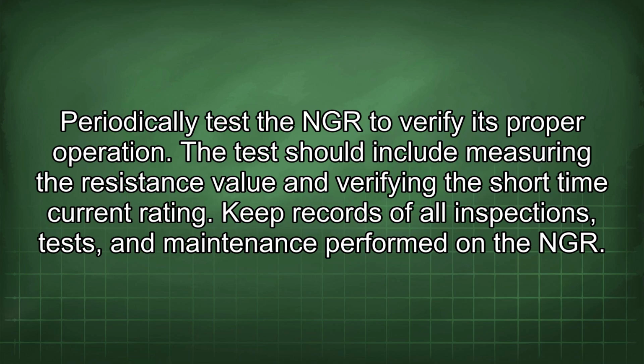Periodically test the NGR to verify its proper operation. The test should include measuring the resistance value and verifying the short-time current rating. Keep records of all inspections, tests, and maintenance performed on the NGR.